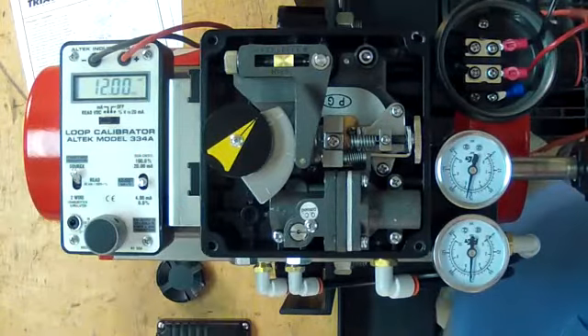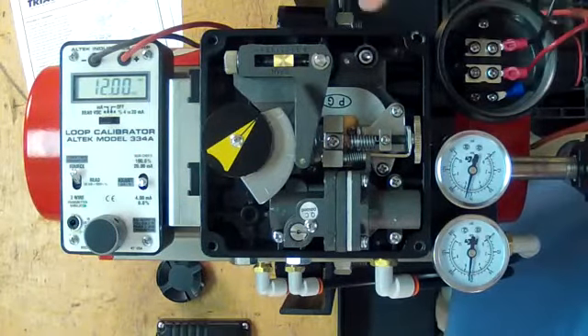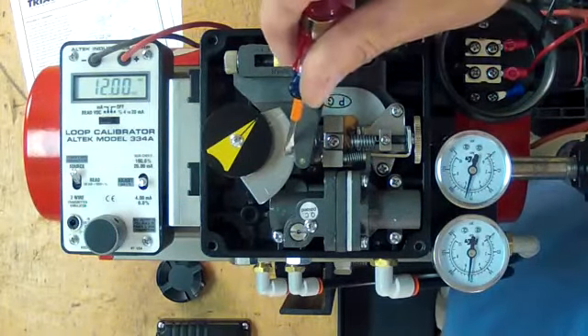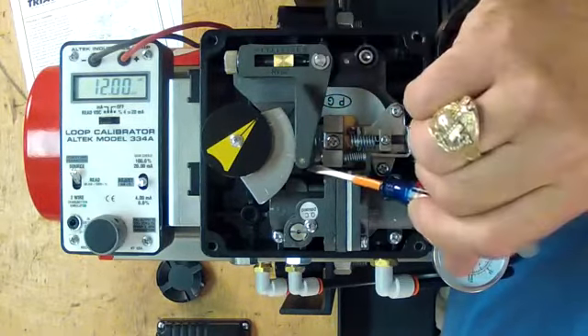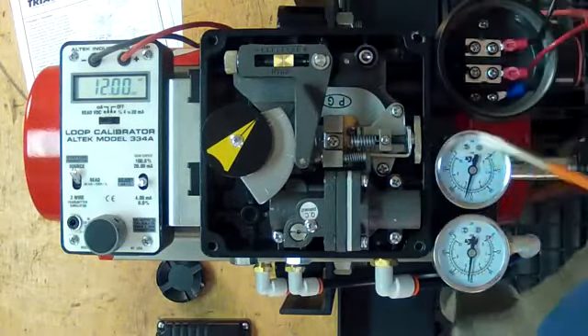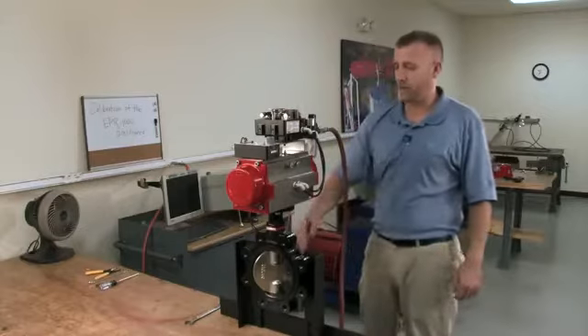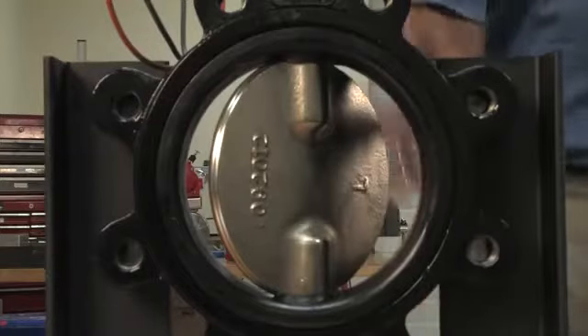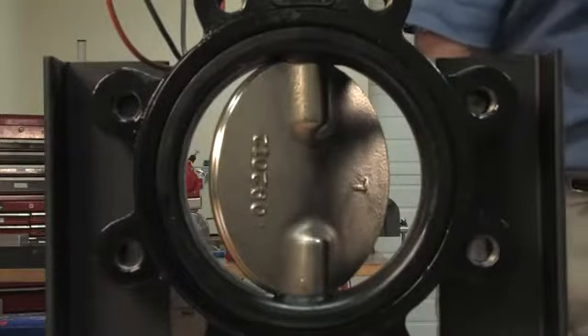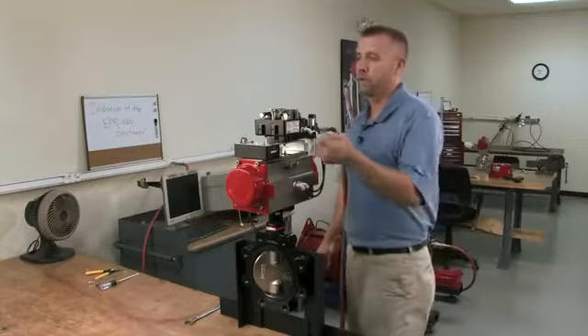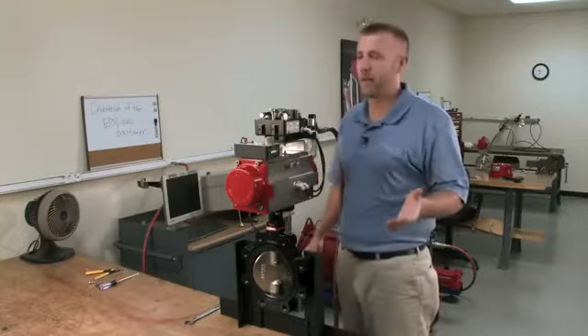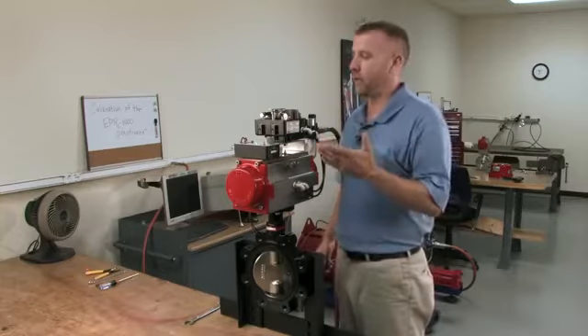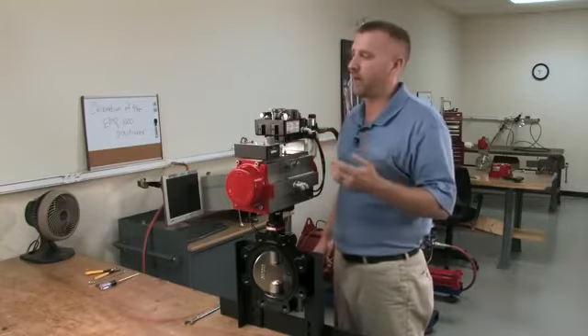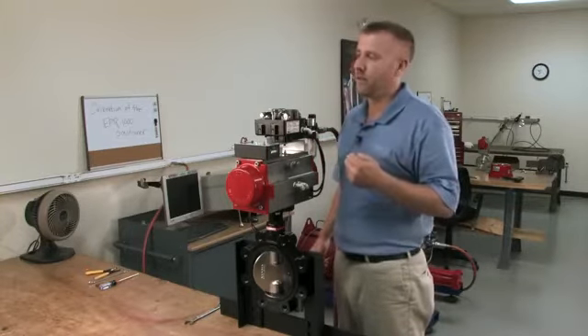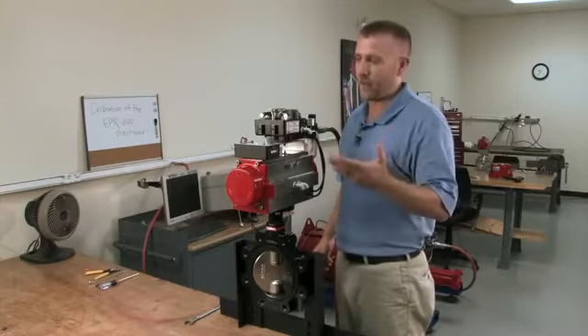And as I stated before, if everything's in line already, you can use this for a base as your midline to your little bearing here. Or, like here, you can simply look at the disc on our valve. You're looking for a 45-degree angle, which that's fine. So at this point, this package is calibrated. Basically, you are adjusting the zero and span, fine-tuning the package to your calibration needs.